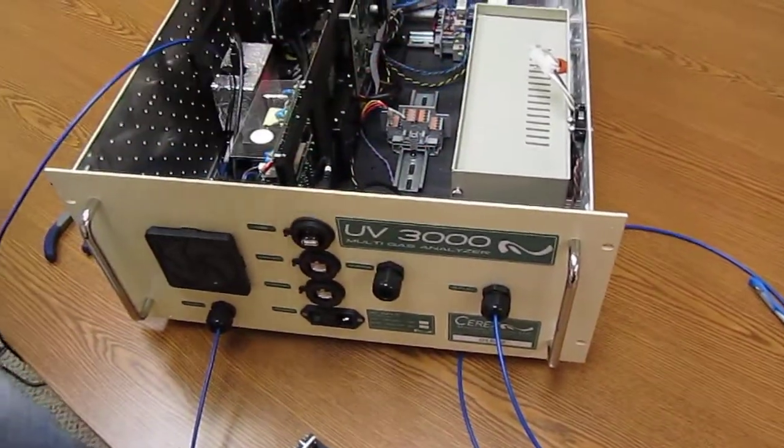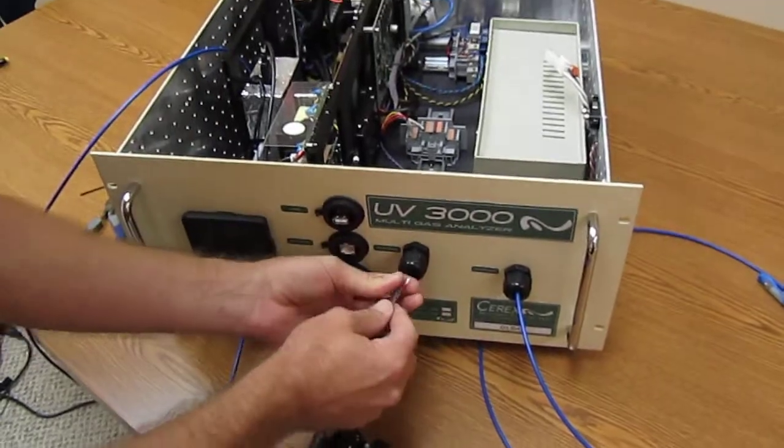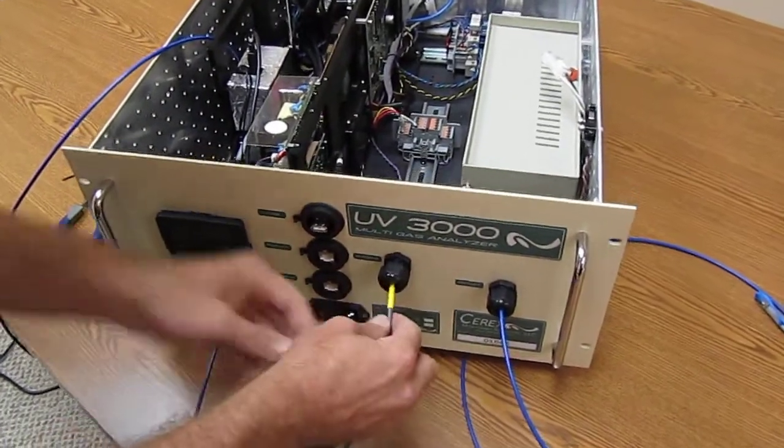To install wire for the 4 to 20 milliamp output, pass the cable through the port on the front of the machine.